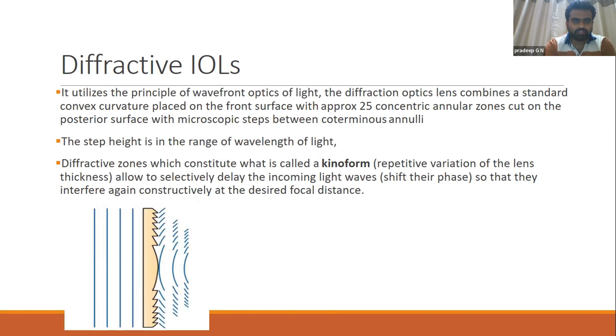Diffractive IOLs use the principle of diffraction and interference, applying wavefront optics of light. The lens combines standard convex curvature on the front surface with approximately 25 concentric annular zones cut on the posterior surface, with microscopic steps in between. The step height is in the range of the wavelength of light. These diffractive zones form what is known as a kinoform, which selectively delays incoming light waves so they interfere constructively at the desired focal distance.